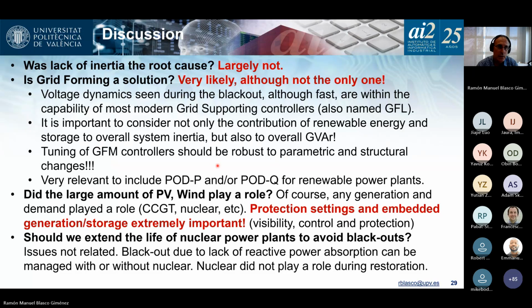That's important. Also, in Spain and in many other places, we have power oscillation damping capability in the grid, but it's not being used in the field. So that was the case in Spain. If renewable energy had contributed to power oscillation damping, probably the initial sequence of events could have been avoided.